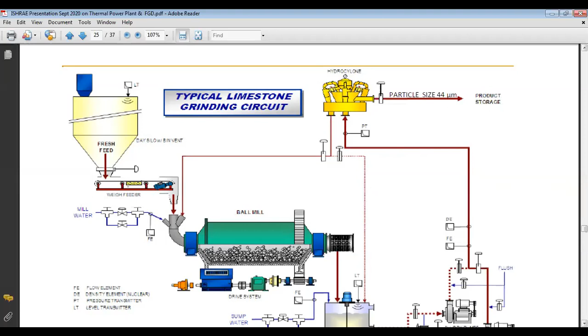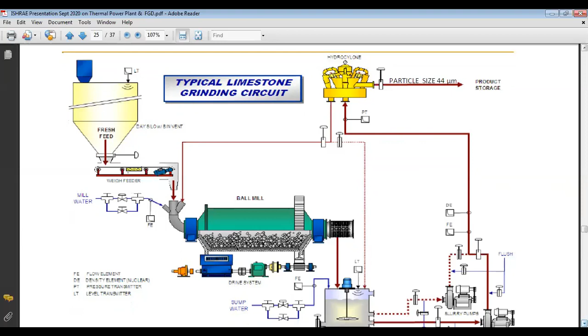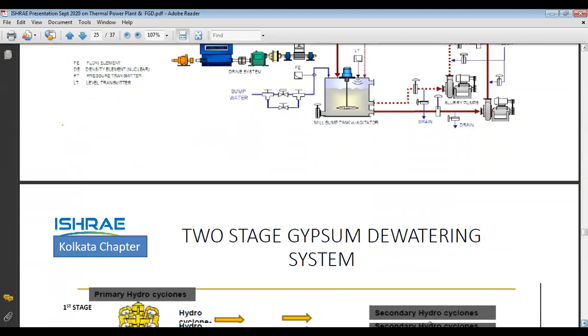The purpose of this hydrocyclone is to pass only the desired particle size, like 44 micron, and above that size, it is again circulated in the ball mill. This is stored in the slurry storage tank. From the slurry storage tank, it goes to the absorber for reaction. The gypsum formation takes place in the absorber, and that is pumped to the dewatering system.